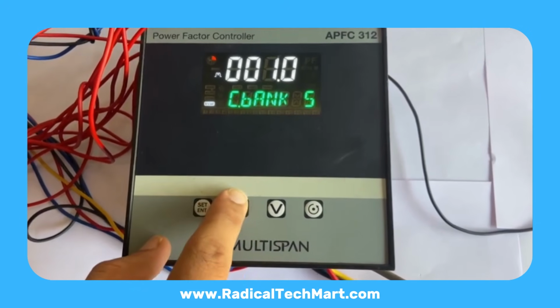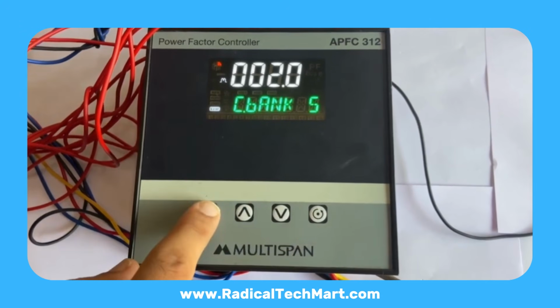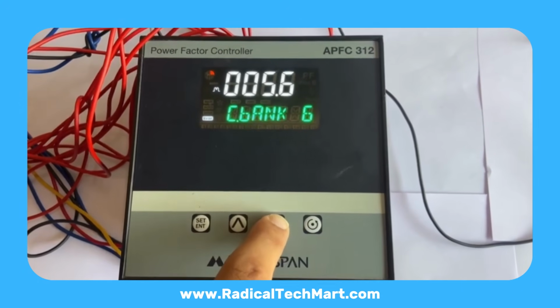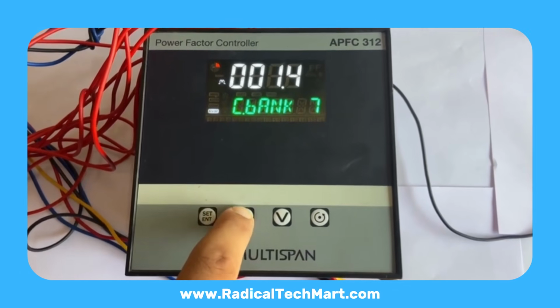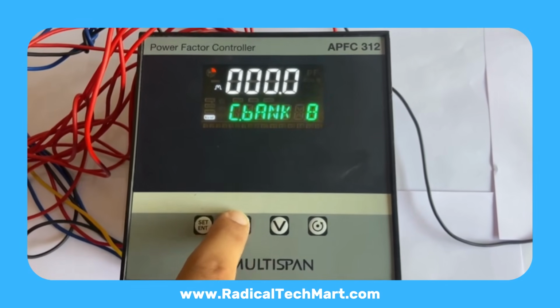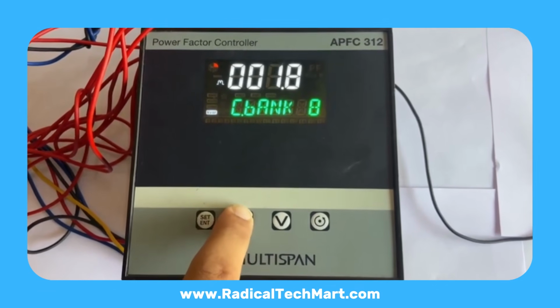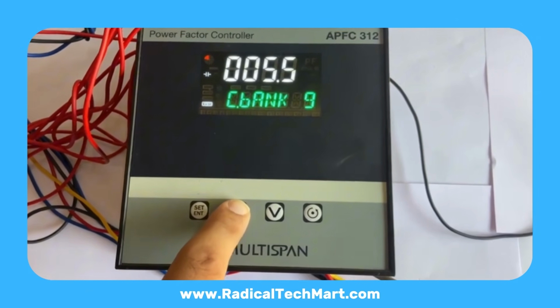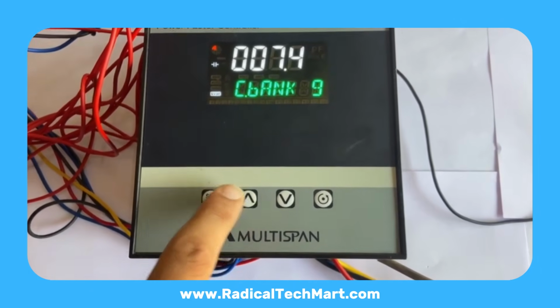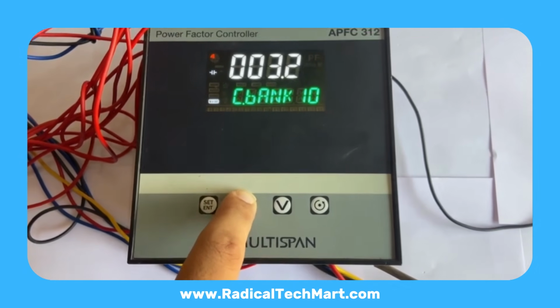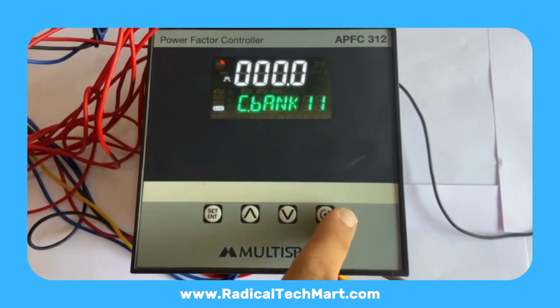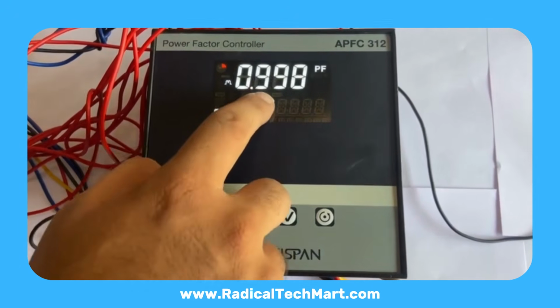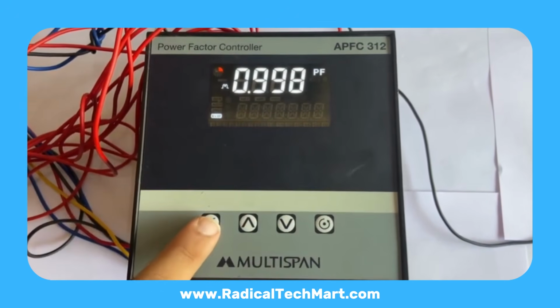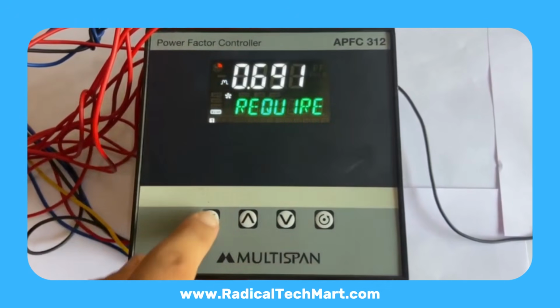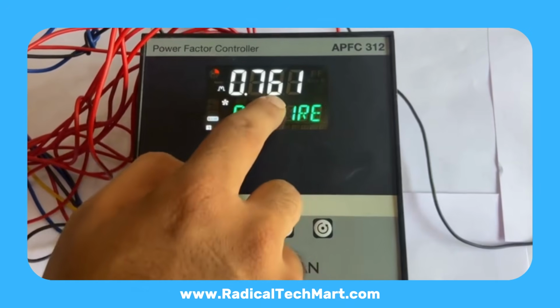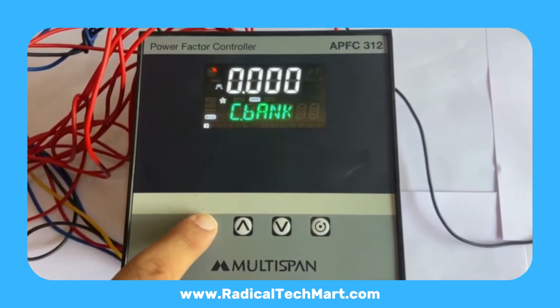Step 5, 2 kilovolt ampere reactive. Step 6, 5 kilovolt ampere reactive. Step 7, 5 kilovolt ampere reactive. Step 8, 7.5 kilovolt ampere reactive. Step 9, 10 kilovolt ampere reactive. Steps 10, 11, 12, 0, not installed. Press set after each value. Your target PF, set PF, is also shown here. Our current set PF is 0.98.